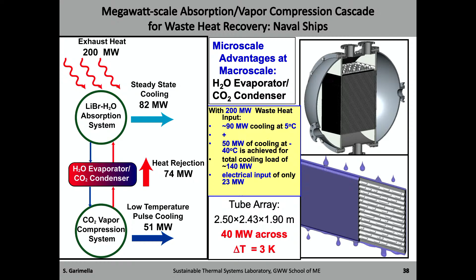Take an aircraft carrier, for example, where it has something like 300 megawatts of heat input, and 200 megawatts of it goes away. That exhaust heat we use to run an absorption heat pump system, and then we coupled it to a vapor compression system, a CO2 vapor compression system, to use 200 megawatts of heat to produce 90 megawatts of cooling at 5 Celsius, and 50 megawatts of cooling at minus 40 Celsius for some challenging cooling needs, by using only about 23 megawatts of electricity.